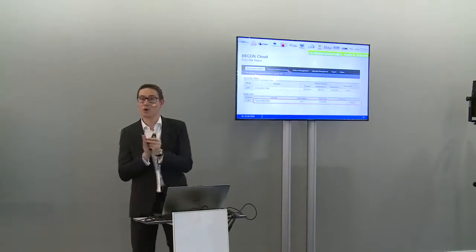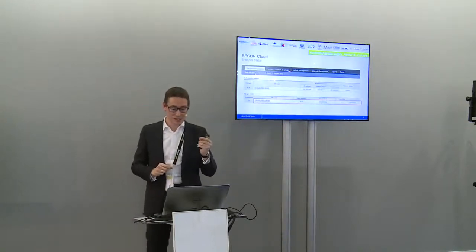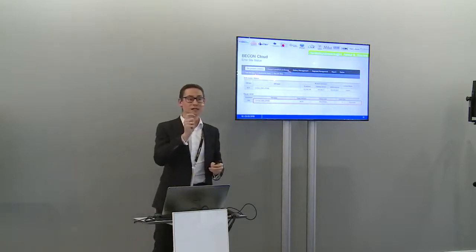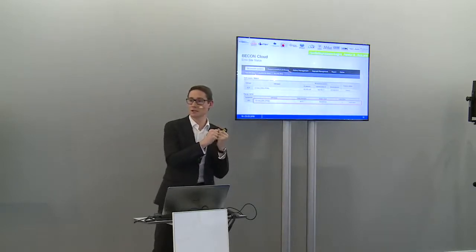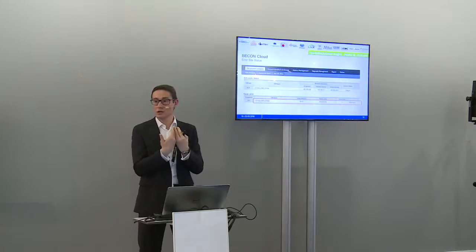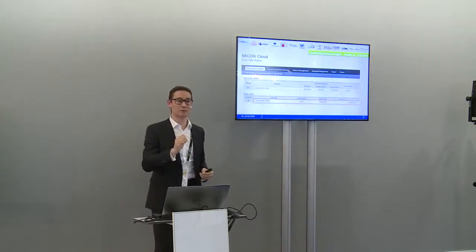In the VRF solution manufacturers, we have the CH error codes. Error code means one failure in the installation that has a meaning. In that example, we are using the CH error code number 4, and number 4 means a failure in the drain pump. So the people that are doing the maintenance of the building can have, from remote sites, knowledge of what is happening in a real installation. And this is a specific error code that reports the exact information on the site.